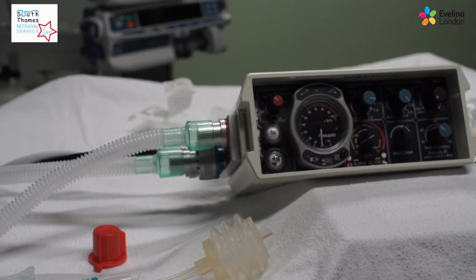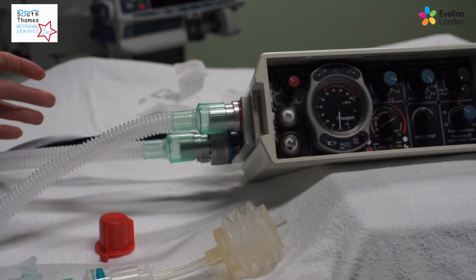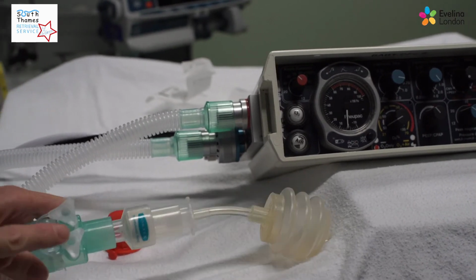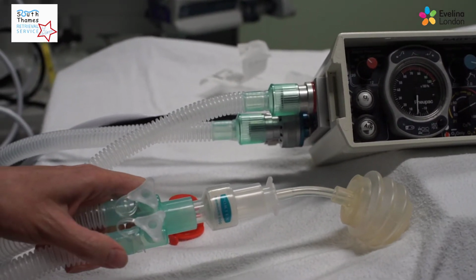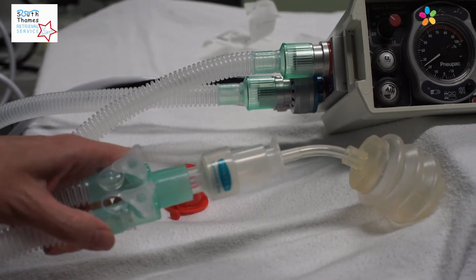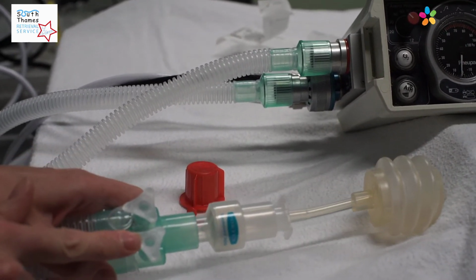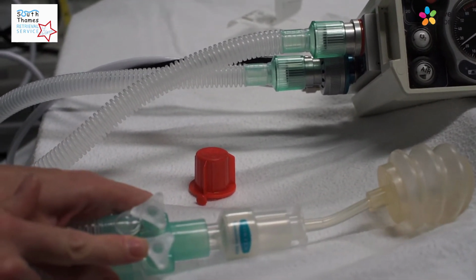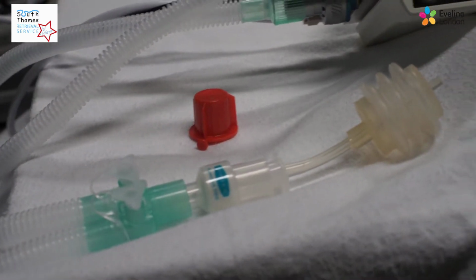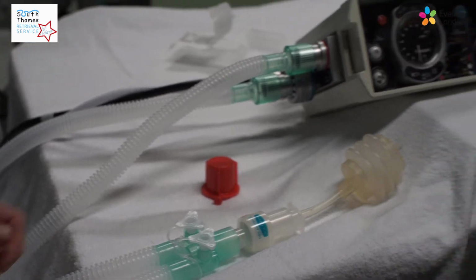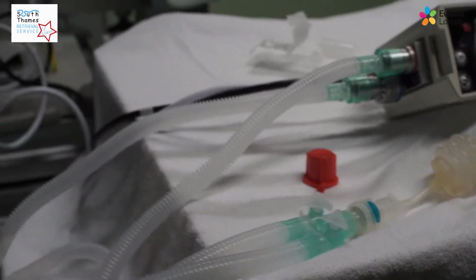Troubleshooting the ventilator is very straightforward. There's very little that we can start adjusting. It's always important to make sure these two plugs are in the hole. That's a common error when the ventilator isn't working properly. Other errors include holes in the tubing that haven't previously been detected, and you can spot those by running your hands along and checking if there's any air escaping.